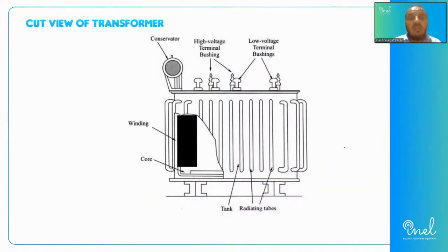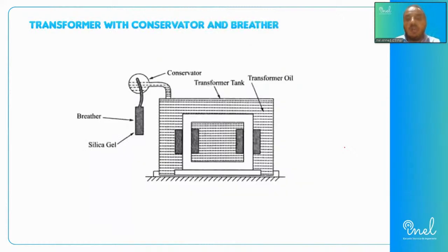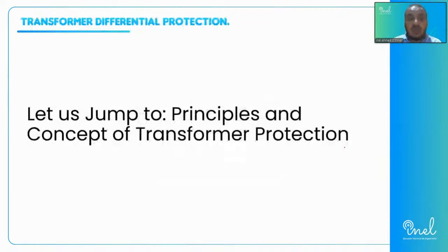We have a cut view of the transformer, where the primary, secondary, high voltage bushing and low voltage bushing are shown. And sometimes we use an oil tank as a cooling system for the transformer. So by such a section, we are getting some idea and digesting the transformer.